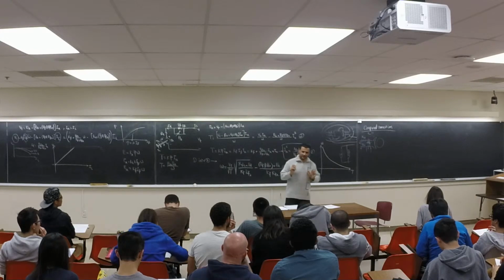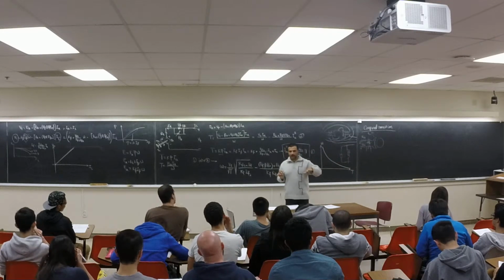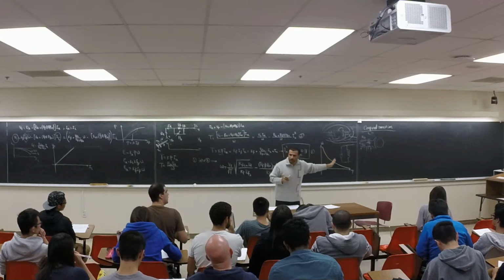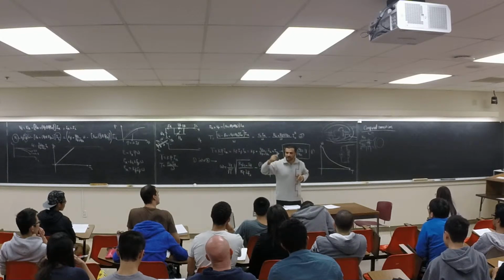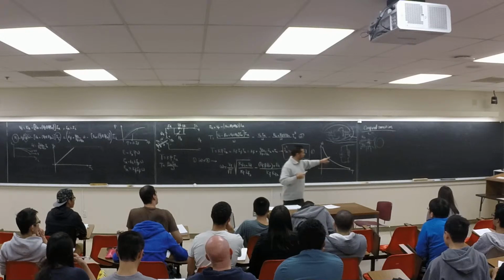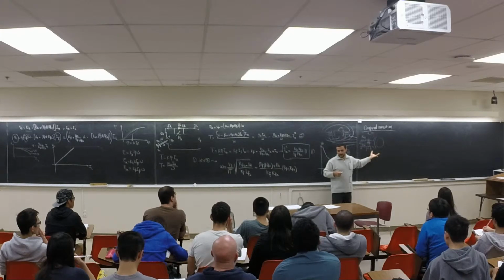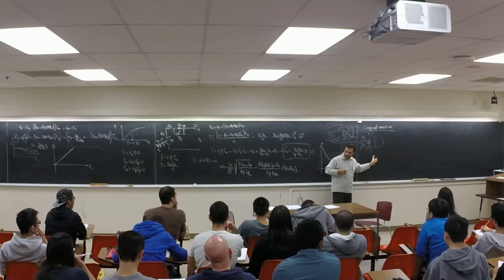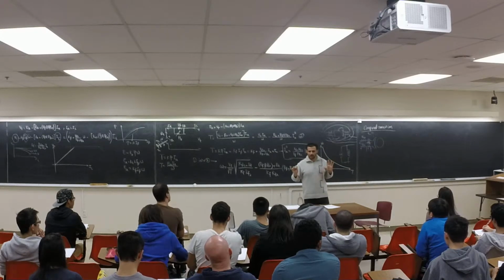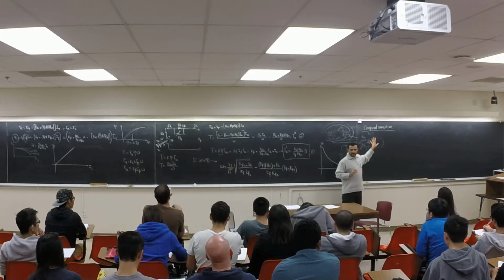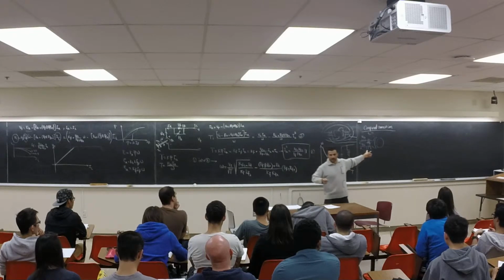We didn't talk about the armature reaction and those kinds of things. I think I'm going to bring one slide finally on Tuesday to talk about that. But armature reaction depends on the armature current. When the armature current is high, the armature reaction is worse. This series winding is in series with the armature; that was the reason we called it series. It carries the armature current, so the field it generates is based on how much armature current we have. If there is no armature current, it's almost zero, as if it's not there at all. When the armature current is high and causing a problem, this one is going to come to help us.